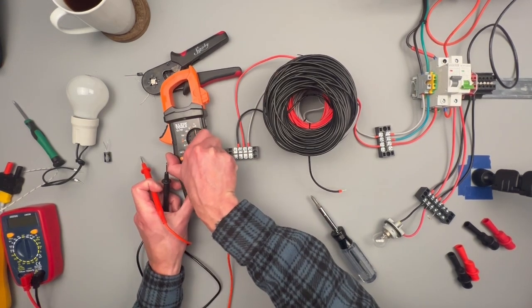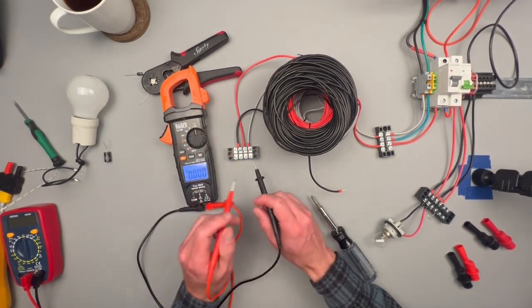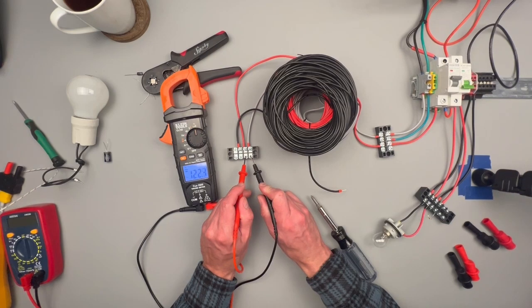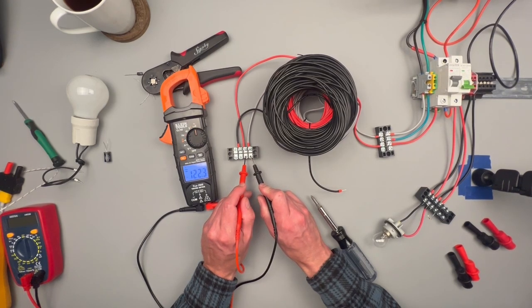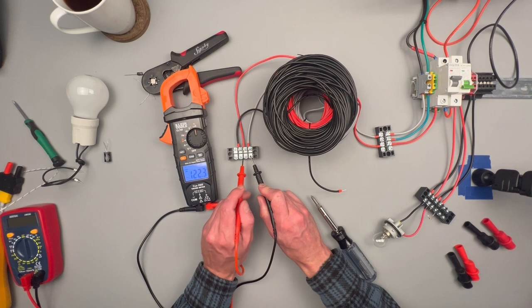If I switch over to this low impedance setting, it's going to set me up for a little tiny load test. And it's going to try to draw maybe a few micro amps. I can still see that I'm showing 120 on my red, but when I switch over to my black, it's going to show no voltage.